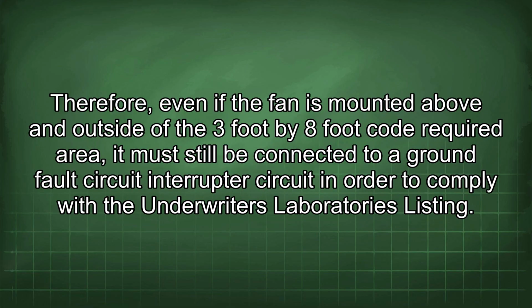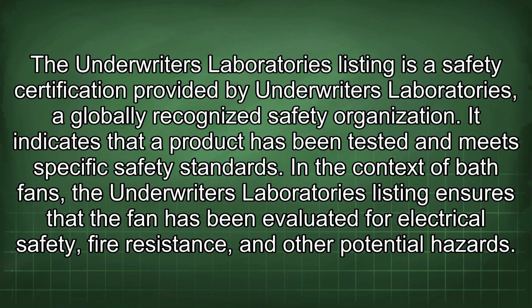Therefore, even if the fan is mounted above and outside of the 3-foot by 8-foot code required area, it must still be connected to a ground fault circuit interrupter circuit in order to comply with the Underwriters Laboratories listing. The Underwriters Laboratories listing is a safety certification provided by Underwriters Laboratories, a globally recognized safety organization. It indicates that a product has been tested and meets specific safety standards. In the context of bath fans, the Underwriters Laboratories listing ensures that the fan has been evaluated for electrical safety, fire resistance, and other potential hazards.